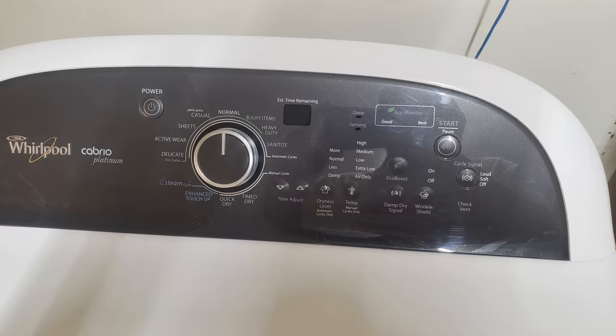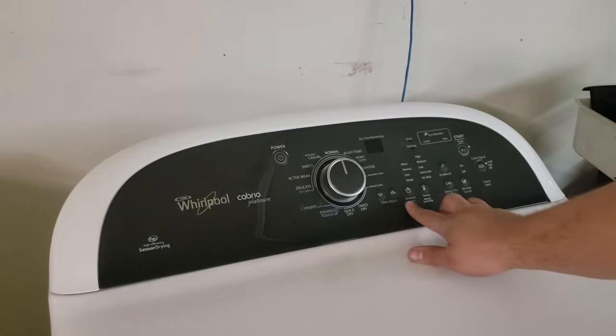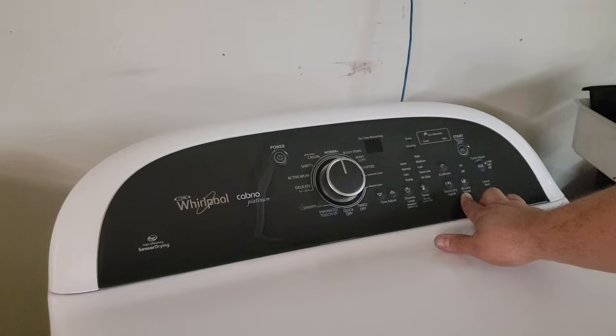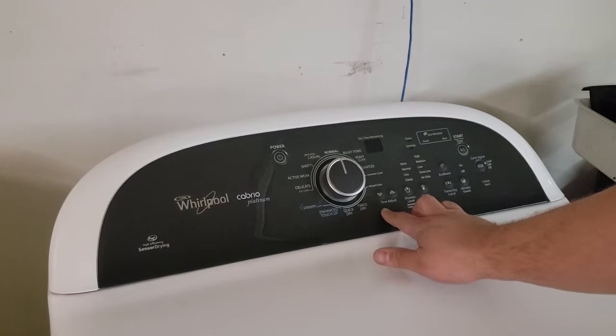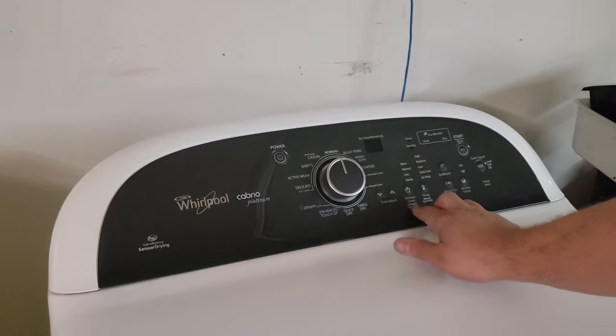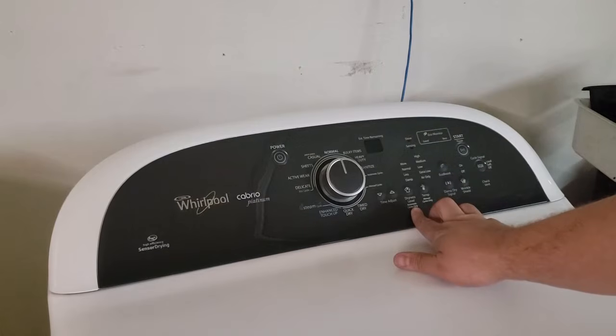To enter diagnostics mode on this style unit, you'll need to pick any three of the buttons that do not include the start button or the power on and off button. Only the green circled buttons are the ones that can be used to enter the diagnostics mode, but make sure to remember which three buttons you press because they will need to be referenced to make any choices inside the diagnostics mode once you've finally activated it. Once you've selected the buttons that you're going to use here, you need to press them in an order of 1, 2, 3, 1, 2, 3, 1, 2, 3 within 8 seconds.